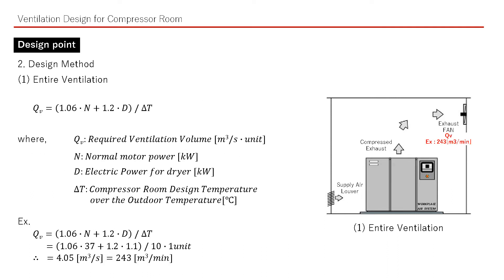We can calculate the required ventilation volume from this formula. Where QV is the required ventilation volume, N is the normal motor power, D is the electrical power for the dryer, and delta T is the compressor room design temperature over the outdoor temperature. As an example: when N is 37 kW, D is 1.1 kW, and delta T is 10 degrees for 1 unit, then QV is 243 m³ per minute. Of course, we shall consider a safety factor when selecting a fan.